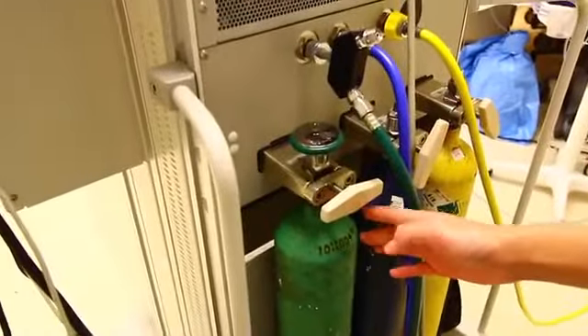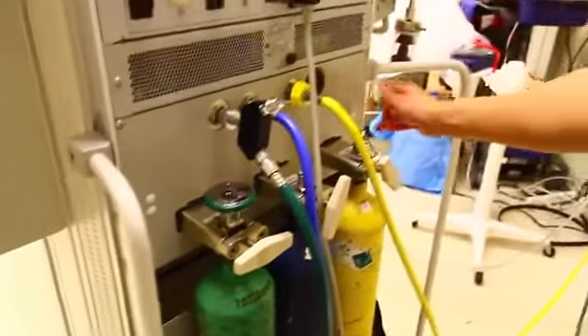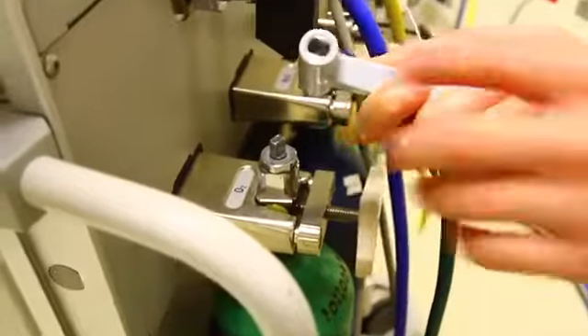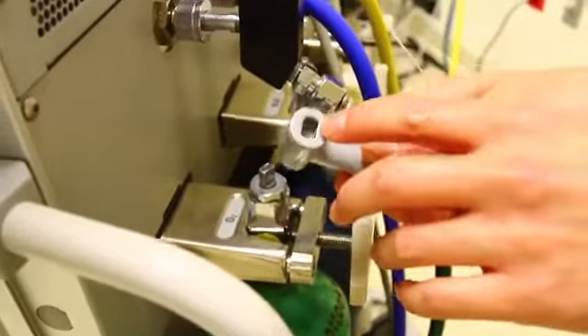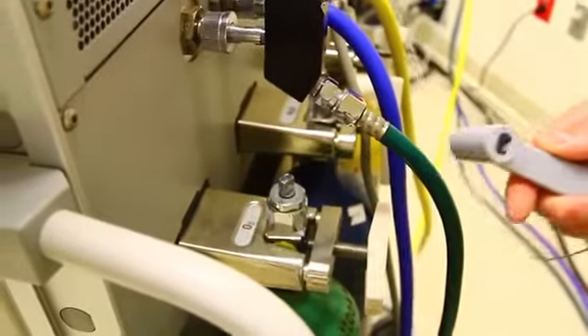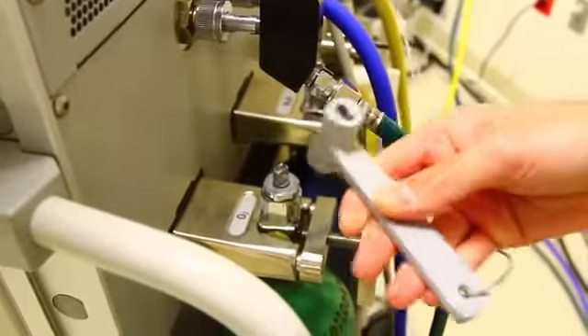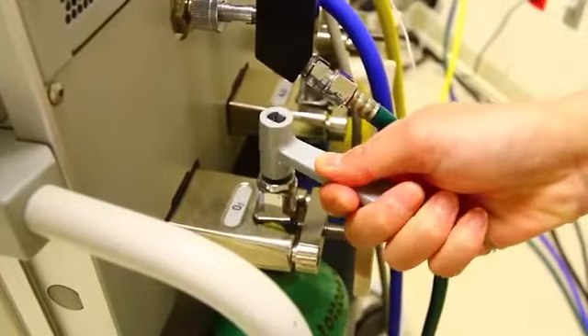The next thing we will do is do a high pressure system check. The backup cylinders are usually on the back of the machine. There is usually a chuck key hanging on the back of the machine. The chuck has different hole configurations to allow you to attach them to the tank valve. To open the tank, you turn the chuck counterclockwise.